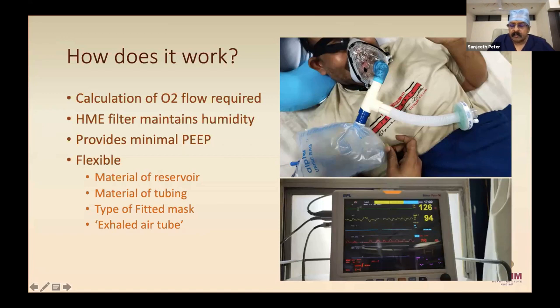The type of fitted mask again can be changed. Ensure that it has only one entry and there are no exits all the way around. If you see small ports there, those are for giving oxygen directly. Yes, you can give oxygen directly, but there's no place where you can have a reservoir for the oxygen, and hence you need this reservoir here. So ensure that those ports, if there are any, can be closed. If there is an exhalation valve within the mask itself, it has to be closed.